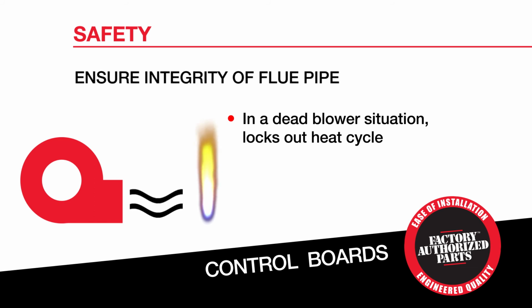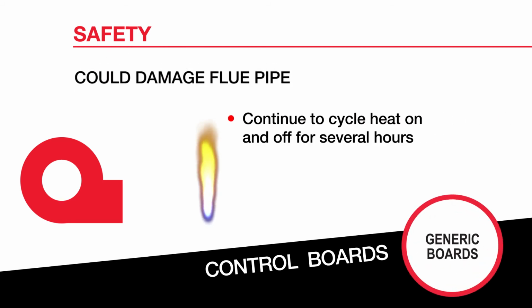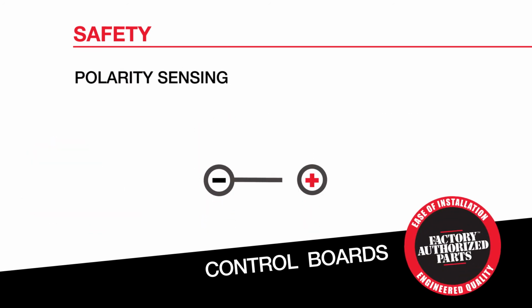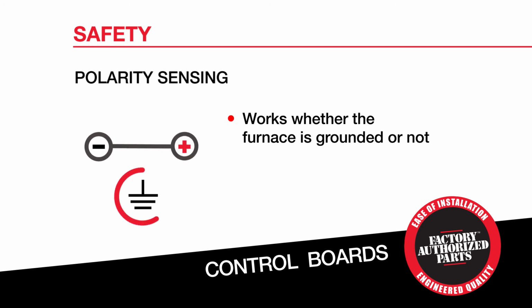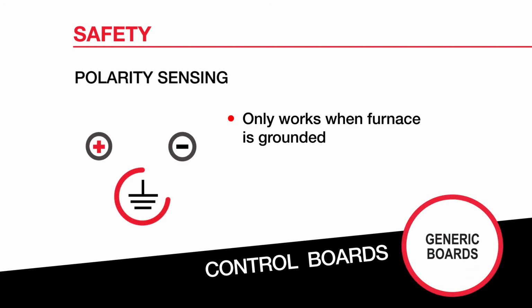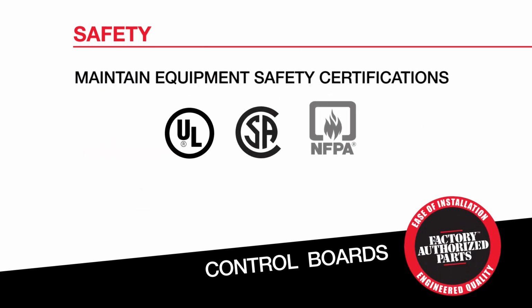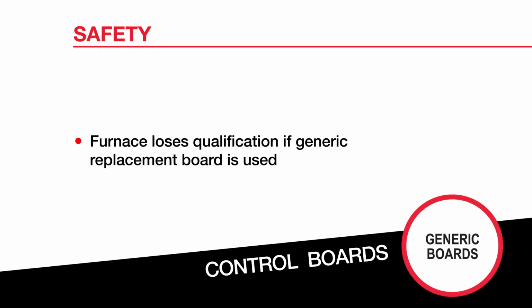In a dead blower situation, factory authorized parts control boards will ensure the integrity of the flue pipe by locking out the heat cycle. Some generic boards could cause damage to the flue pipe because they may continue to cycle heat on and off without locking out for several hours. Then there's polarity sensing. With a factory authorized parts board, polarity sense works whether the furnace is grounded or not. On some generic boards, the polarity sense only works when the furnace is grounded. Finally, factory authorized parts control boards maintain equipment safety certifications. Even if the aftermarket part is qualified, the furnace won't be if you use a generic board as a replacement.